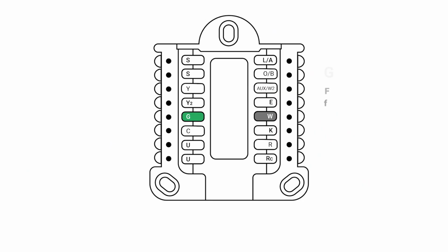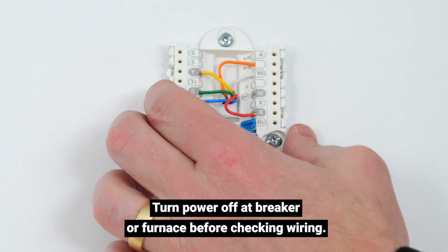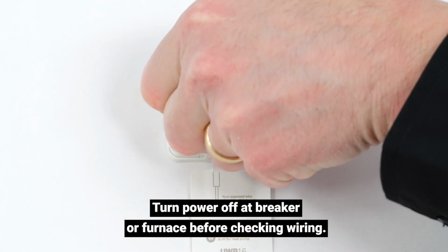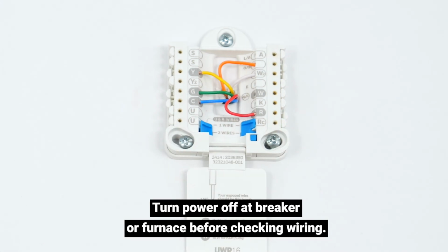Is the fan on your HVAC system not running? Start by changing the fan mode from auto to on, on the screen of your thermostat. If your fan is still not running, let's check the wiring. Fan operation is controlled by the G terminal on your thermostat. Forced air systems typically have a G wire, but many radiant heat or hot water systems don't. Based on your system type, confirm the G terminal is wired and has good contact.